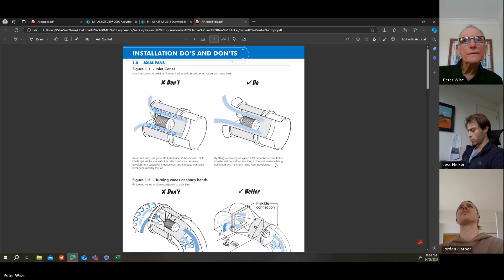Install tips, I've called it. So this is from the Fantech catalogue. They've got some good information in there. Flexible, so you can see on this one, see where they put the flex, it's an axial fan. There's a transition, they put the flexible connection back here. On this one, don't do this. Don't have a sharp bend, a flexible connection, and straight onto the fan.